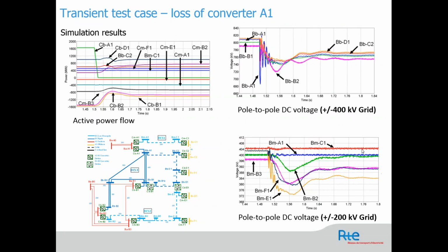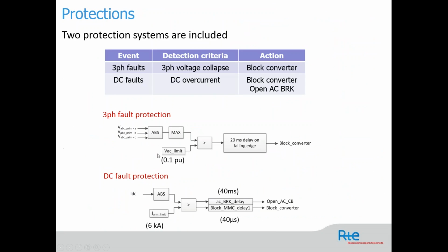Regarding MMC protection: why are the MMCs blocked when AC voltage is lower than 0.1 per unit? Should the MMC be able to ride through zero AC voltage? Thanks for this question. He's asking about the AC protection threshold of 0.1 per unit. This depends on the AC system, the project requirements, and the TSO requirements. Usually at RTE, the TSO we use 0 per unit, meaning 0% residual voltage.